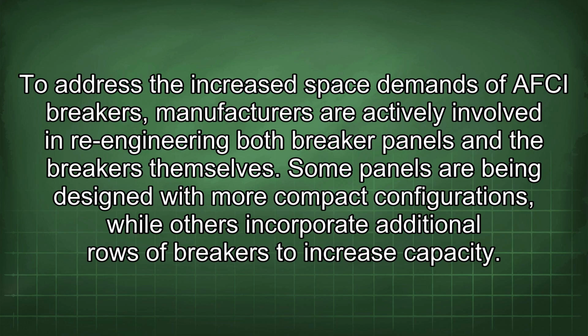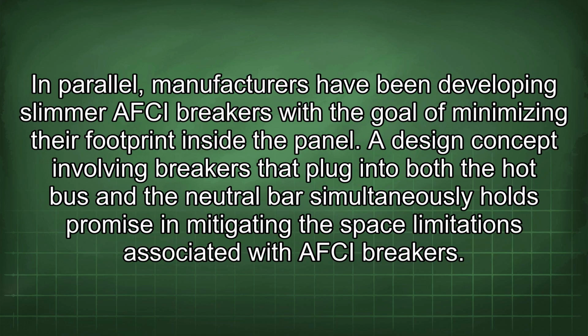To address the increased space demands of AFCI breakers, manufacturers are actively involved in re-engineering both breaker panels and the breakers themselves. Some panels are being designed with more compact configurations, while others incorporate additional rows of breakers to increase capacity. In parallel, manufacturers have been developing slimmer AFCI breakers with the goal of minimizing their footprint inside the panel.